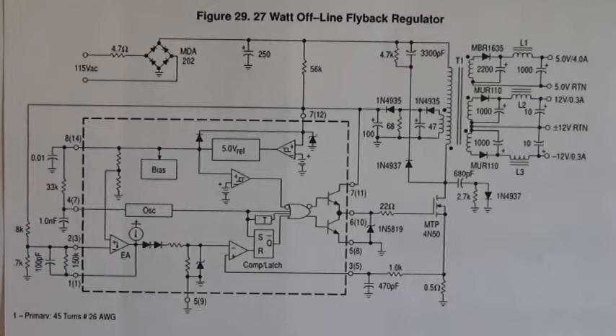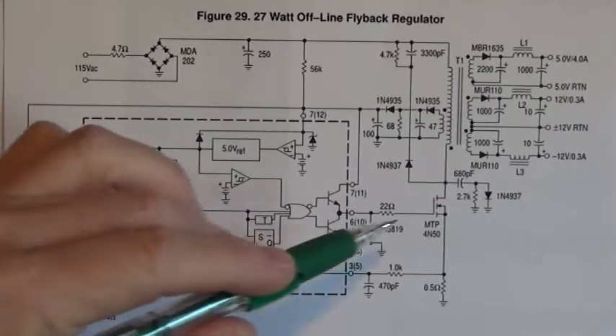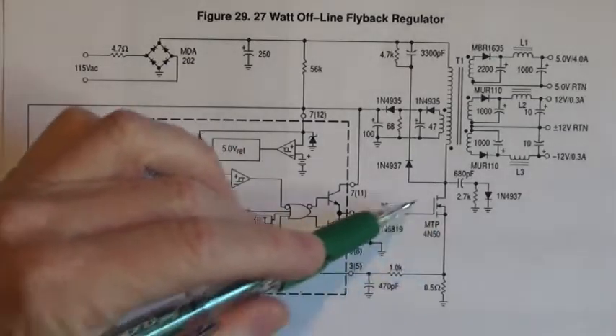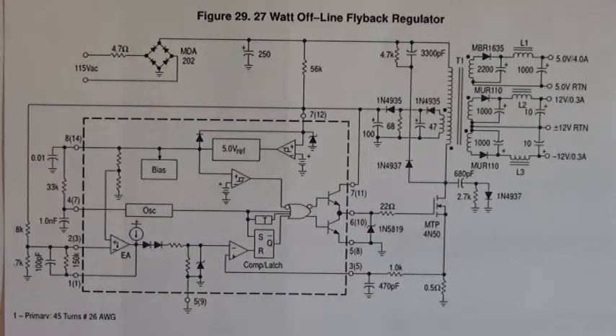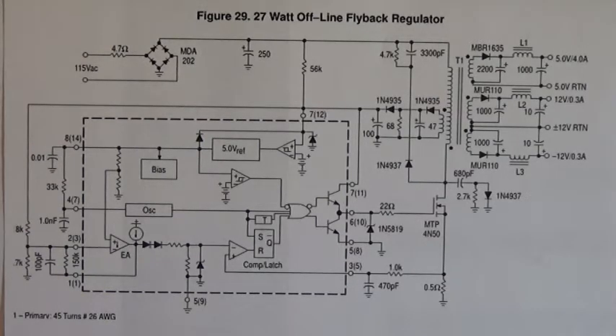The next thing, the most common failure in switch mode power supply circuits, is the power MOSFET. It will fail, it will short. That power MOSFET right there, or it can be a power transistor, it works hard. And it works hard 24 hours a day.